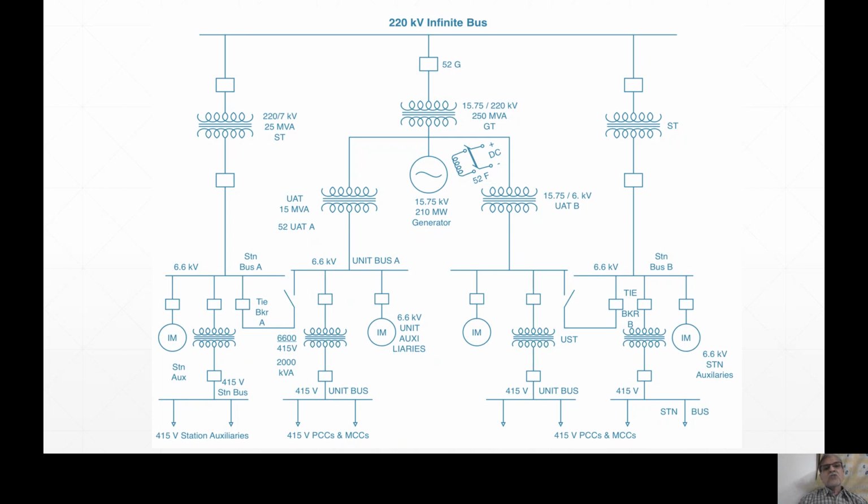Why at all? The 22 states were affected. There was no power in 22 states. Complete blackout for some 5 hours or so. So, what is the reason? Everybody was interested. And the reason was purely power system protection. It was load encroachment, I told you while I was discussing distance protection. It started with load encroachment.